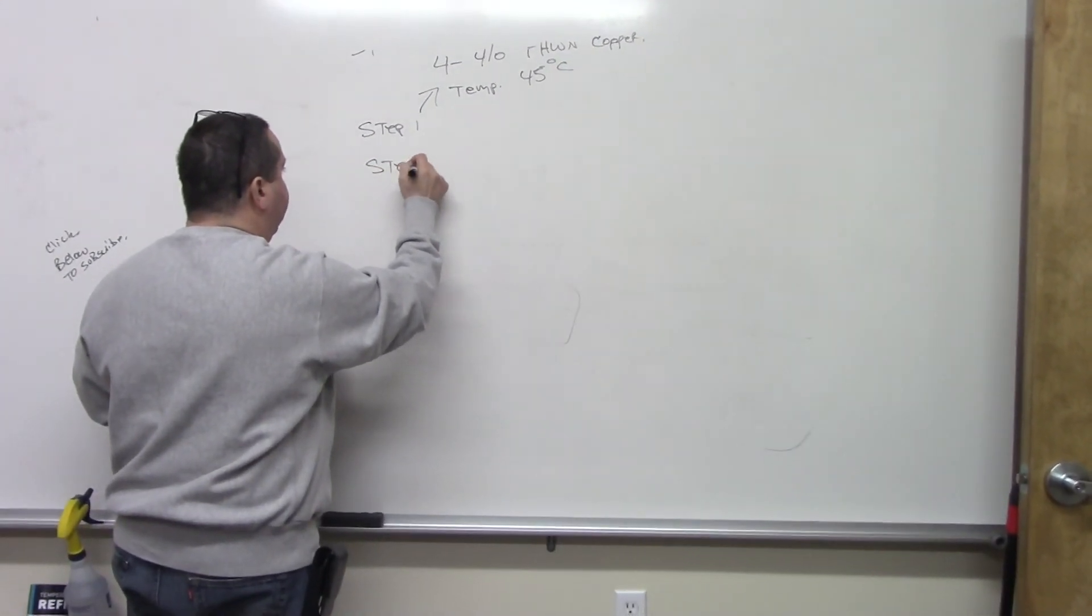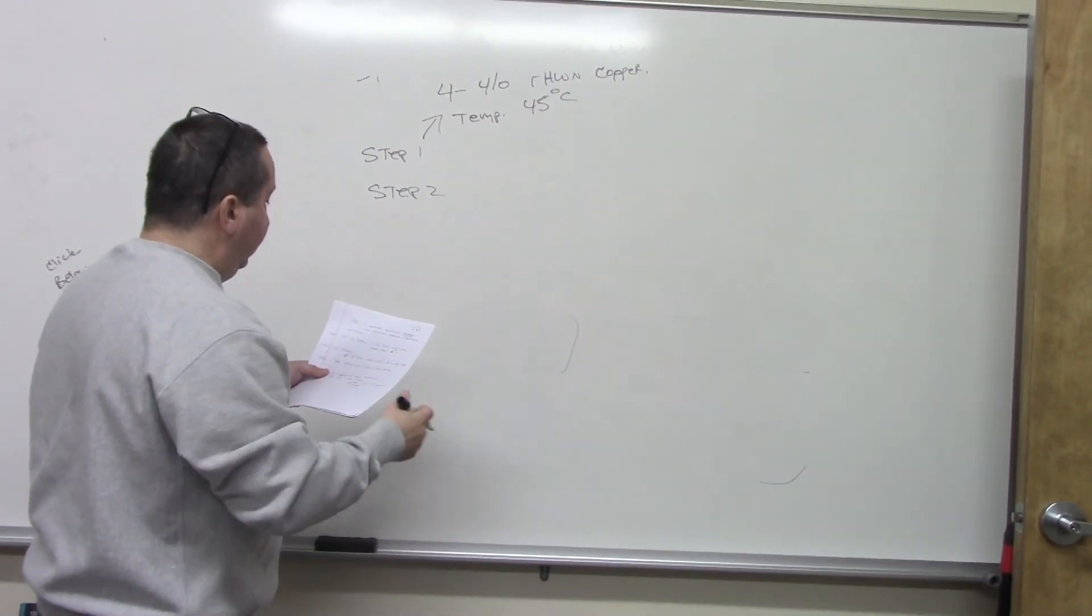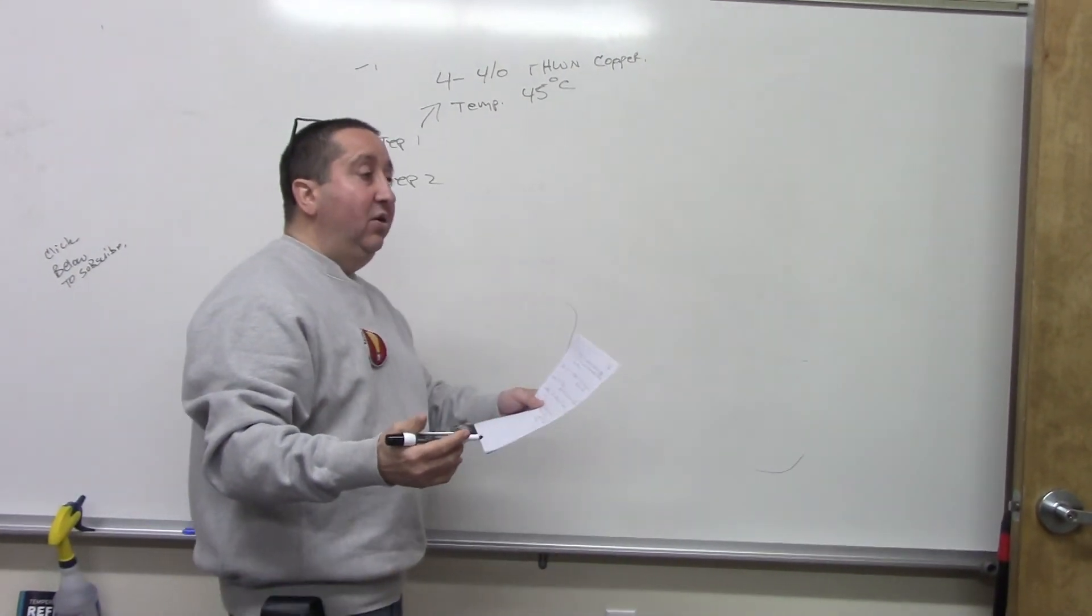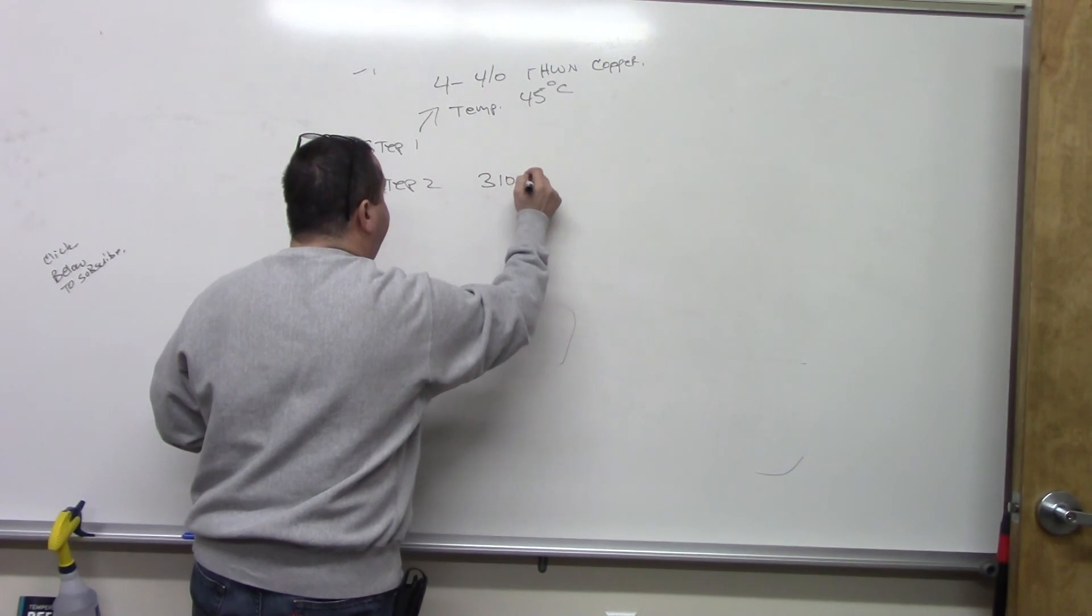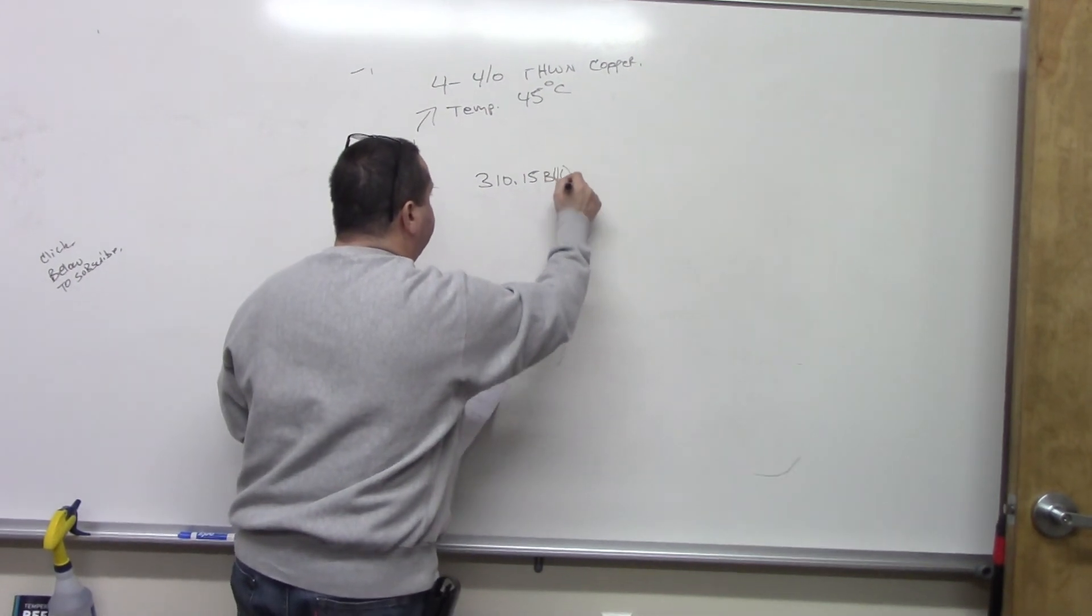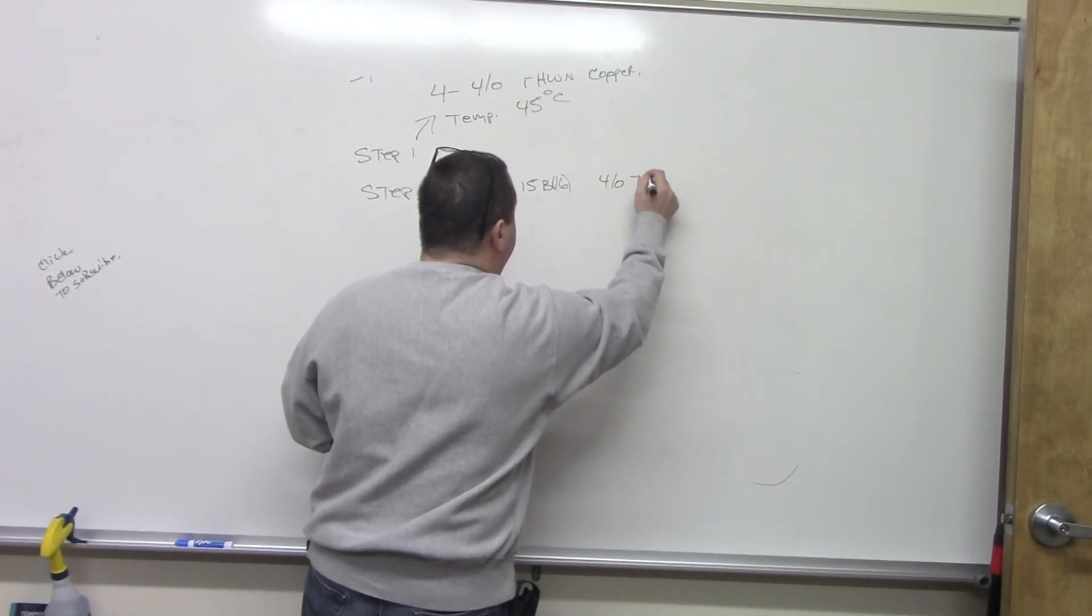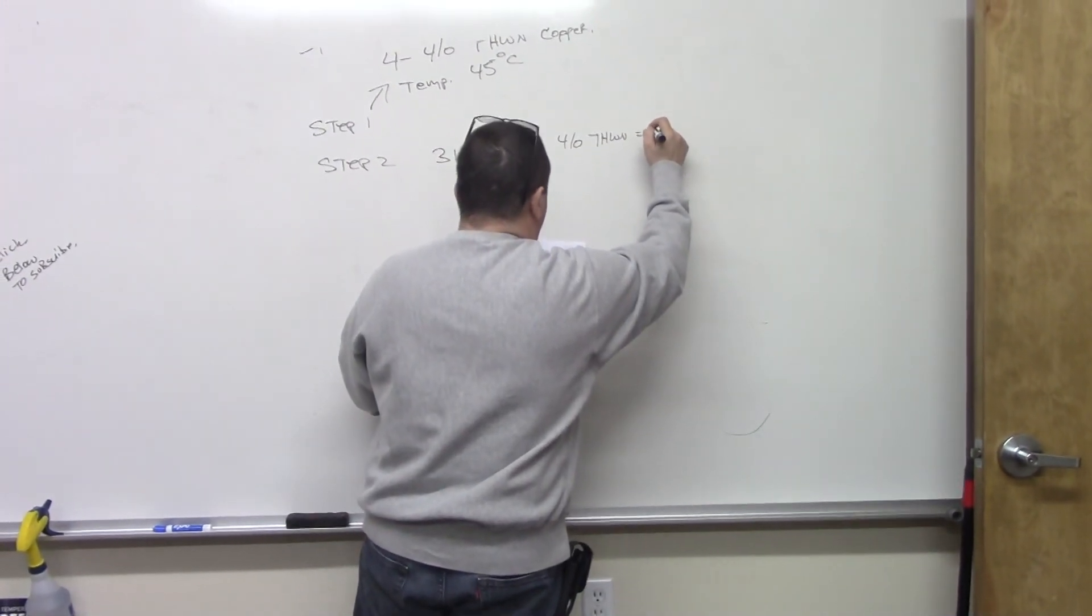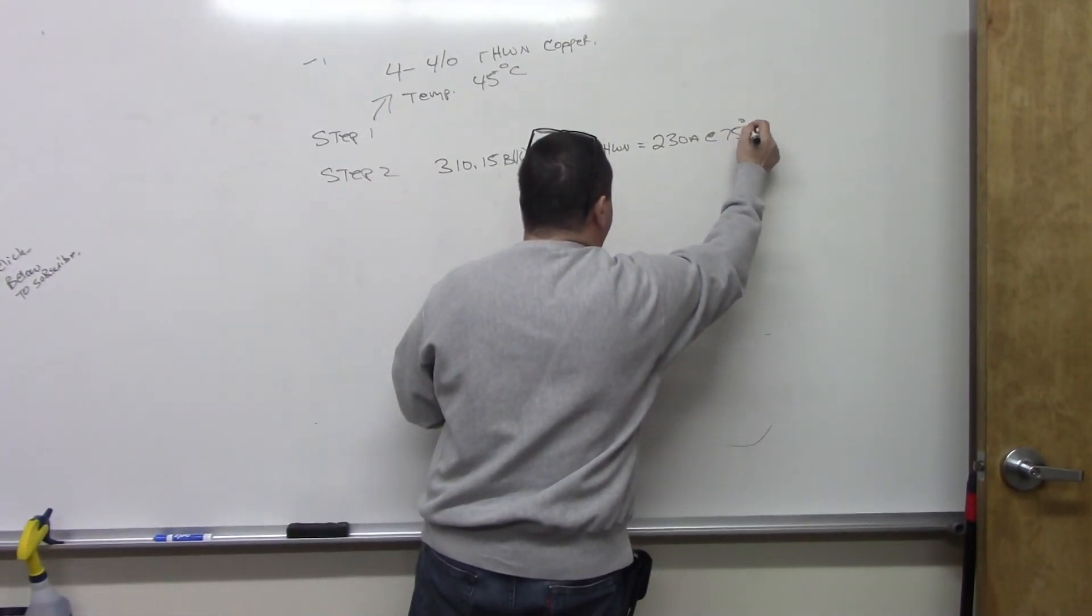Step two is we're going to find out what a 4/0 AWG THWN copper ampacity is, and then what's the adjustment factor for it. For the ampacity, we go to Table 310.15B16.